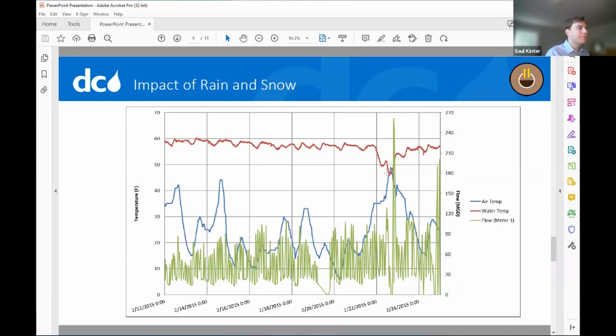First, the minimum temperature here is 46, which is not that bad. It's still warm enough to do pretty good efficiency heating and cooling. Second, we were only at 46 for a very brief time. The mean temperature over this excursion was more like 50 or 52, and that, again, is pretty good.